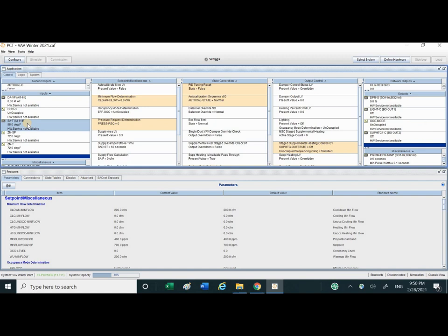Supply air temperature, this is the RTD, the default value is 55 Fahrenheit. And this one is the room temperature set point. The default value is 72, and the zone temperature is what the thermostat senses. If the set point is equal to or lower than the zone temperature, then the output heating is off. These are all inputs and these are all outputs. Now we simulate, and we manually change these values and then see what the output is.